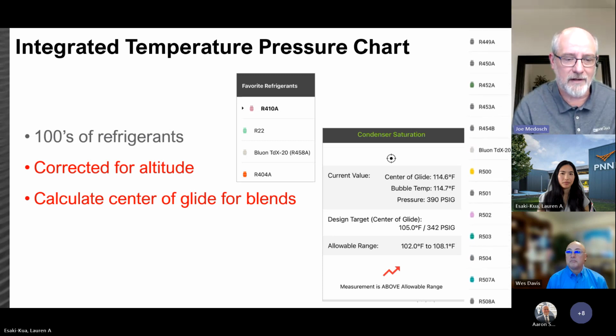So if you see on that graph on the right, it says center of glide, 114.6, and the bubble temperature. These are all things very specific to that refrigerant at that altitude that are being calculated. I can just say MeasureQuick is the only one that really does this type of calculation, providing this level of accuracy.